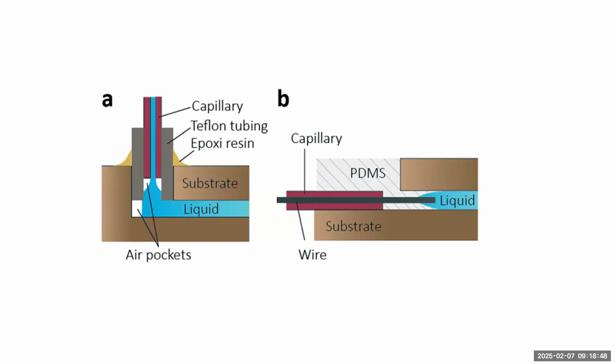So you have pressure drops automatically. Also, pressure is directly correlated with velocity and fluid volume. So as your volume increases, say going from a skinny little capillary tube into a larger area in a device, you're going to have a pressure drop. Again, pressure drop and heat don't automatically cause bubbles, they cause them to grow.